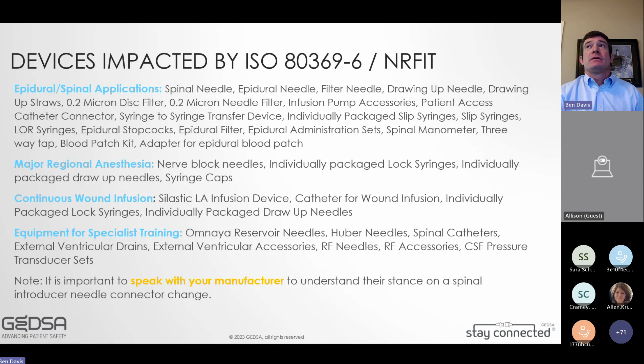Not to go into every little micro application here, but just high level, the devices that are impacted by ISO 80369-6, NRFit: you have your epidural and spinal applications, major regional anesthesia, continuous wound infusion, and then there's equipment for specialist training. And then to visualize some of these components, you have slip tip syringes. Here you see your Luer version. Your NRFit version, the nozzle is a little bit smaller, but has the same ID. And it actually has a collar around it, so you won't see an exposed tip like you have with the Luer slip.